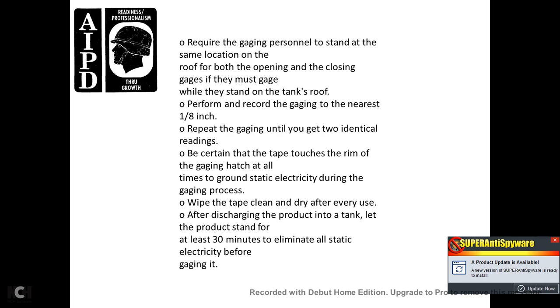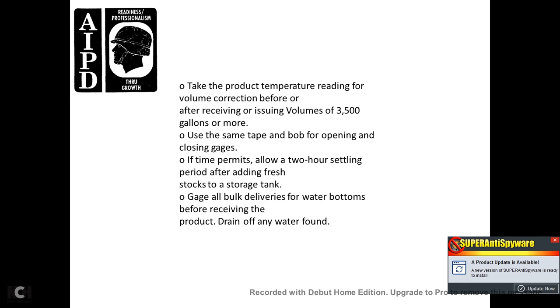Be certain that the tape touches the rim of the gauge hatch at all times to ground static electricity during gauging. Wipe the tape clean and dry after use. After discharging product into a tank, let the product stand for at least 30 minutes to eliminate all static electricity before gauging. Take product temperature readings for volume correction before and after receiving or issuing volumes of 3,500 gallons or more, using the same tape and bob for opening and closing gauges. If time permits, allow a two-hour settling period after adding fresh stock to a storage tank. Gauge all bulk deliveries for water bottoms before receiving the product.